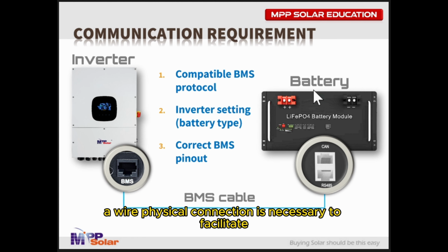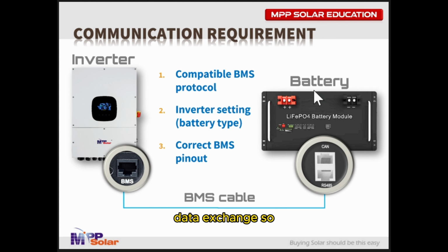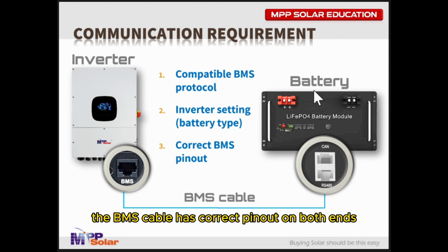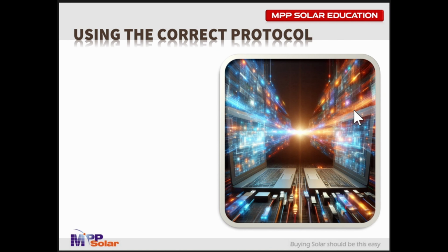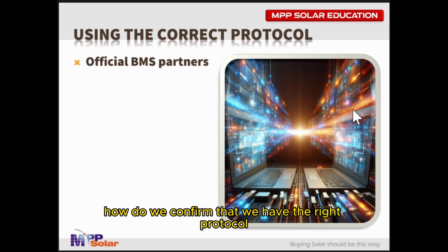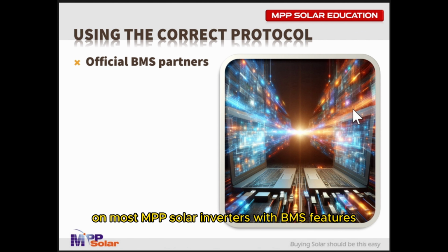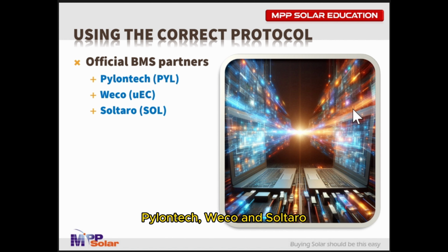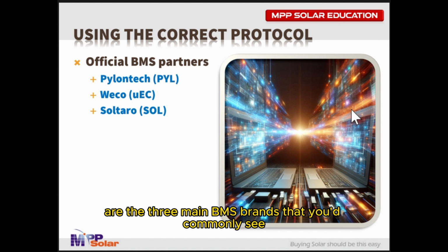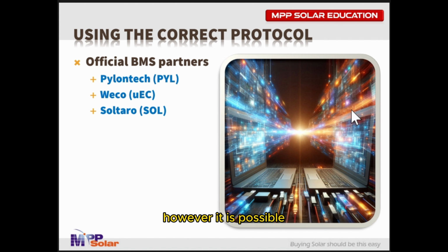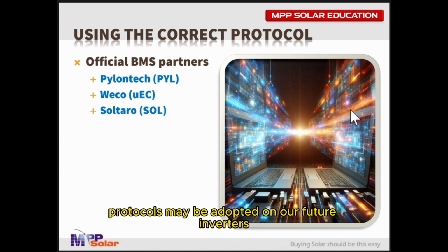Finally, a wired physical connection is necessary to facilitate data exchange, so we need to make sure the BMS cable has the correct pinout on both ends. So back to the first requirement, how do we confirm that we have the right protocol? On most MPP Solar inverters with BMS features, Pylontech, Weco, and Soltaro are the three main BMS brands that you'd commonly see. However, it is possible more BMS protocols may be adopted on our future inverters.